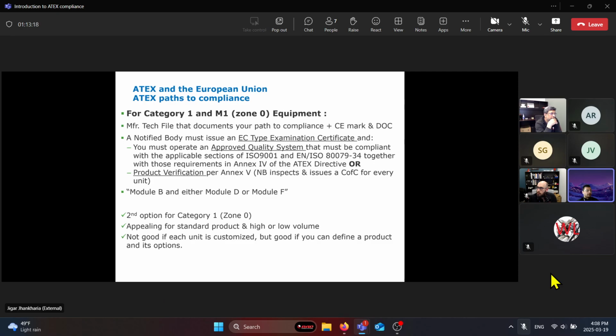Again, talking about category 1, zone 0 equipment requires an EU type examination certificate. If it's for type certification, an approved quality system with ISO 9001, along with the 80079-34, which is the QAR and QAN. So the ISO is the QAR, the EN at the front is for QAN. That's the only difference there.